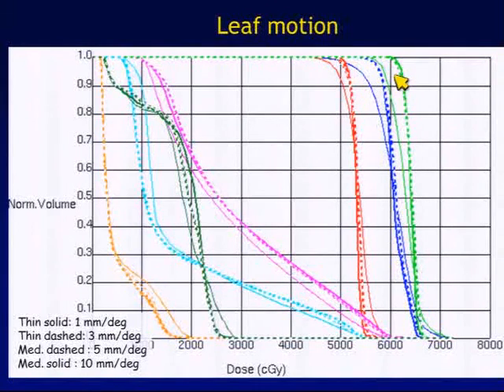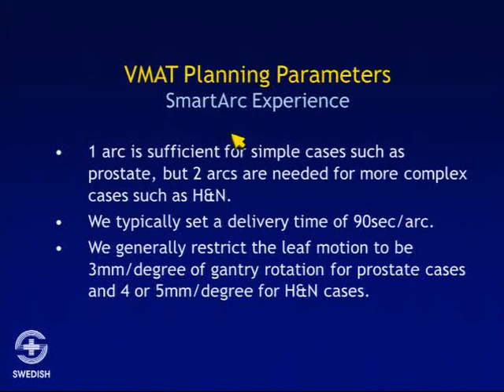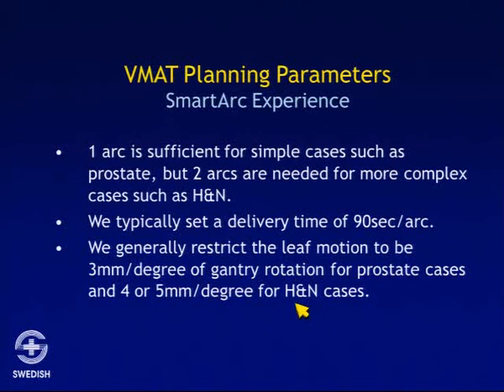In summary for SmartArc parameters: one arc is sufficient for simple cases such as prostate, but two arcs are needed for more complex cases such as head and neck. We typically set a delivery time of 90 seconds per arc, and we generally restrict leaf motion to 3 mm per degree of gantry rotation for prostate cases and 4 or 5 mm per degree for head and neck cases. These parameters will differ from one planning system to the next, but give an idea of what you might be working with in VMAT planning.